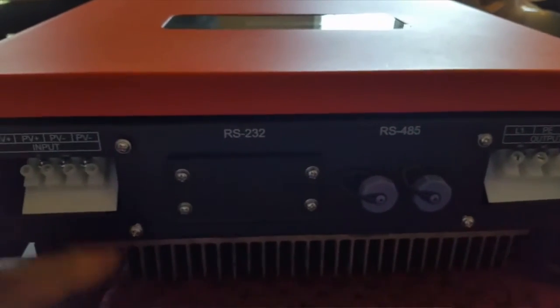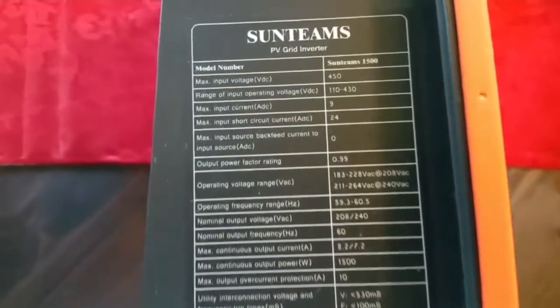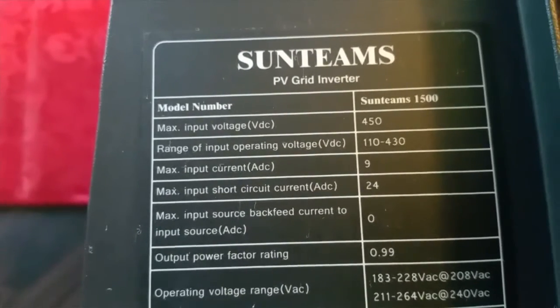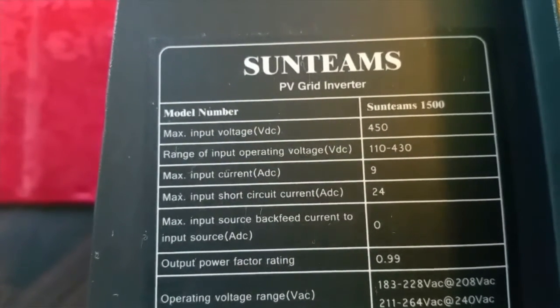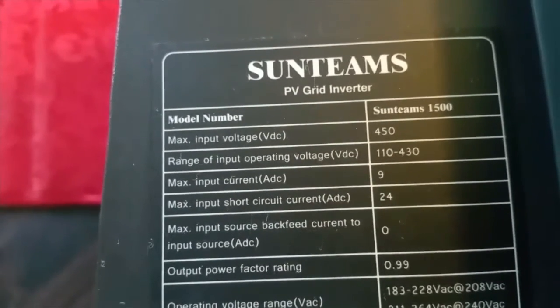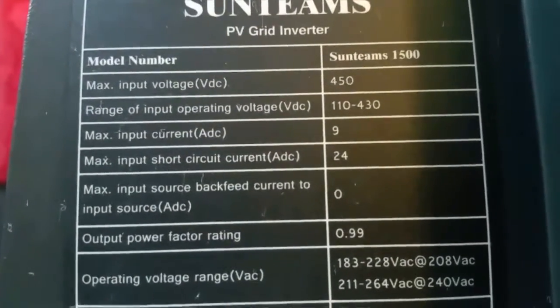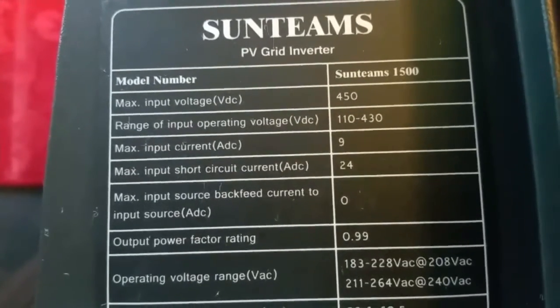These are the specs right here. This device takes a maximum input DC voltage of 450 volts DC. The range of input operating voltage is from 110 to 430 volts, which is a good range for the MPPT to work. The input current is 9 amps. Maximum input short circuit — when you get your solar panels, you have the continuous and the ISC short circuit amps, which are a little bit higher.